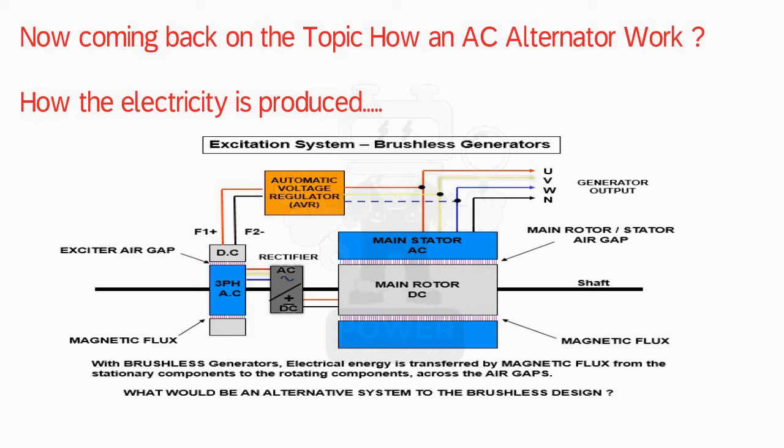The exciter stator produces a DC electromagnet in the coils. Across the exciter air gap we have the exciter rotor, which has three-phase winding. This three-phase output goes to the rectifier assembly — the rectifiers take AC supply as input and give out DC supply to the main rotor. The main rotor then becomes an electromagnet with poles, producing magnetic flux across the air gap. As the main rotor moves inside the main stator, the windings in the main stator are cut by the electromagnet, and electricity is produced.